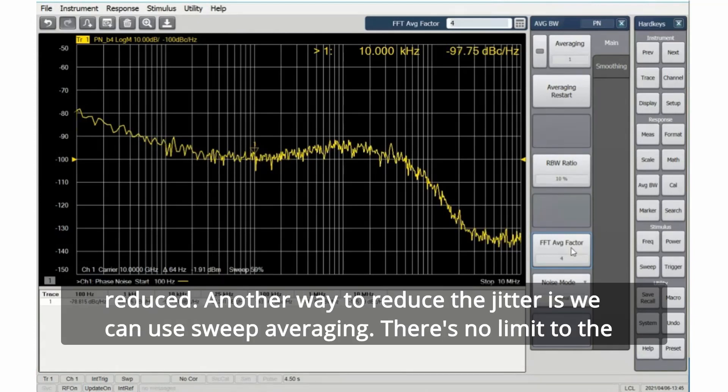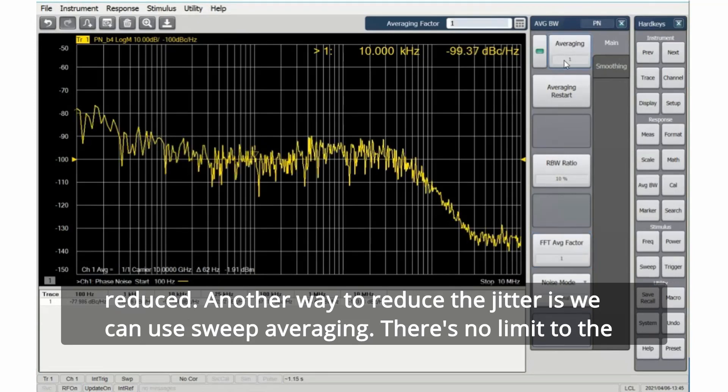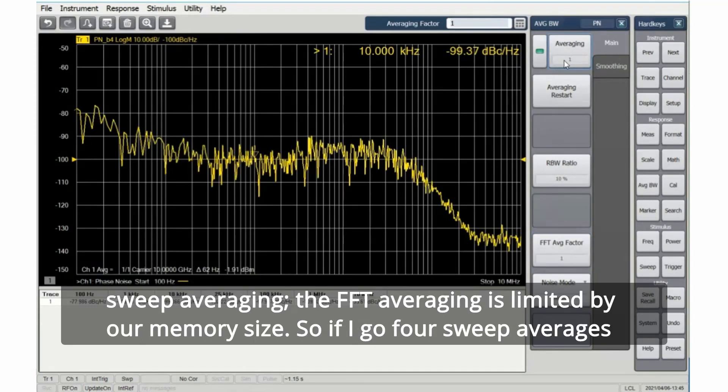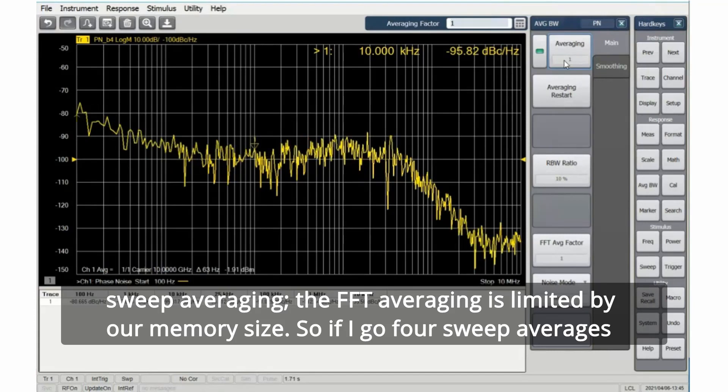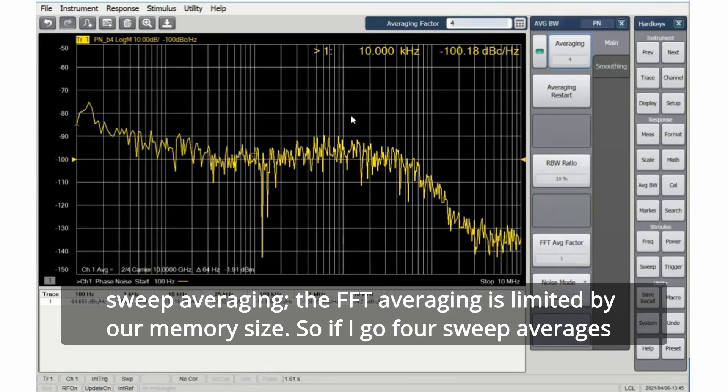Another way to reduce the jitter is we can use sweep averaging. There's no limit to the sweep averaging. The FFT averaging is limited by our memory size. So if I go four sweep averages, then it'll average subsequent sweeps.